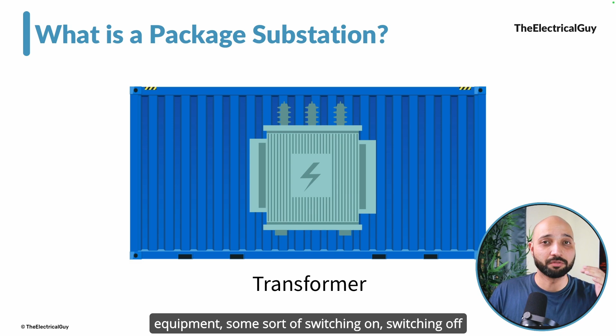But we cannot give supply to the transformer directly - we need some protection equipment and switching equipment. For that, we need medium voltage switchgear, MV switchgear. The supply comes in, goes to this switchgear, and from there to the transformer. This switchgear is generally a ring main unit, or RMU, which is a very important component of the power system, especially the distribution network. If you don't know what a ring main unit is, I have a few videos on that - I'll put the link in the description, you can check it out after this video. So supply is given to the ring main unit, and from there it goes to the transformer.